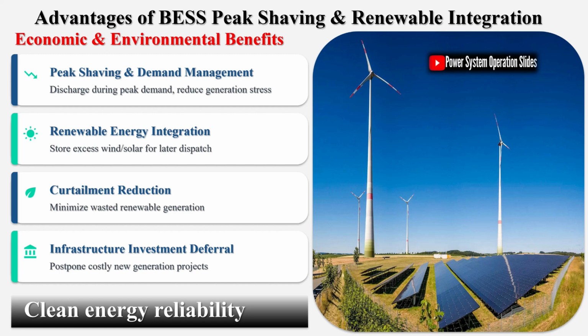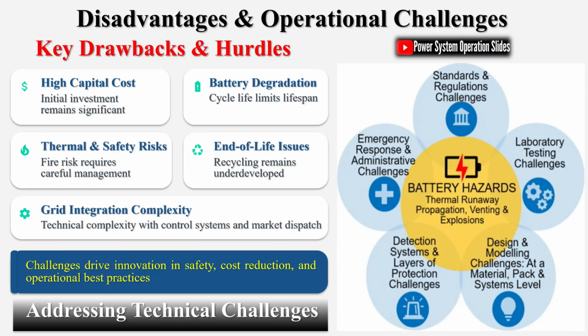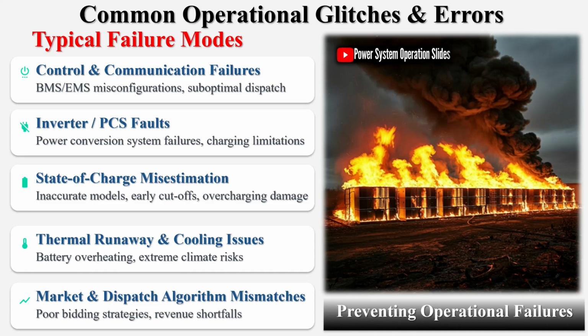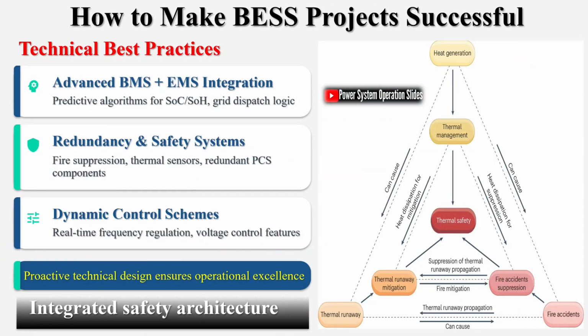The timing of failures provides another critical insight. Approximately 72% of failures where system age is known occur during construction, commissioning, or within the first 2 years of operation. This concentration of failures in the early lifecycle phases underscores the critical importance of integration, assembly and construction as a risk mitigation priority. Many of these incidents occur during the commissioning phase when monitoring and communication systems are not yet operational, allowing leaks or isolation failures to escalate into large-scale fires before detection and intervention become possible.